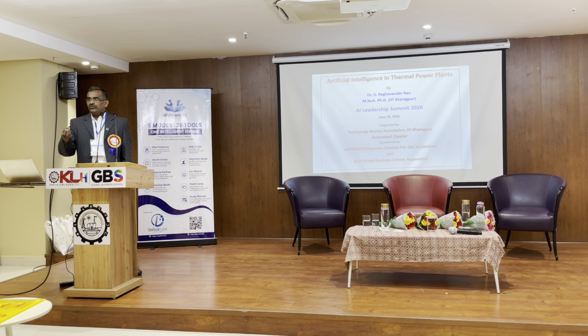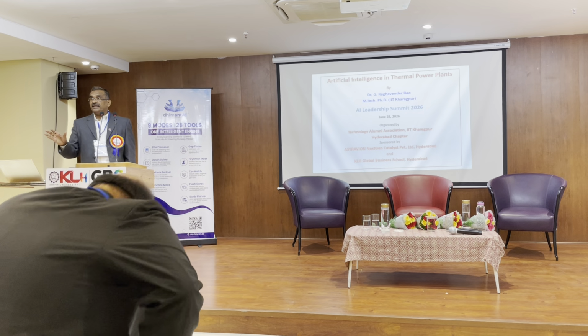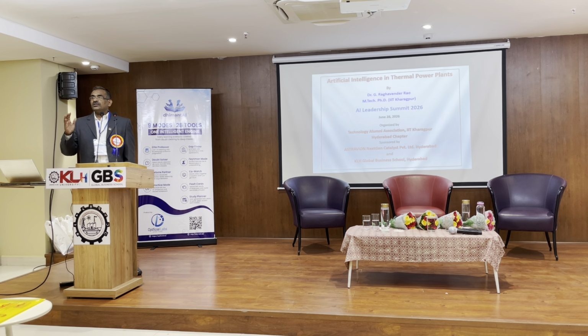If you want to vaporize water, it requires latent heat, which consumes energy. Transferring water to steam below supercritical pressure involves two phases, steam and liquid. But if the pressure is more than 221 bar, water directly converts into steam without requiring latent heat, making the plant very efficient. Higher the pressure and temperature of steam injected into the turbine, higher the efficiency. That's why turbines working with steam above supercritical temperature and pressure are called supercritical thermal power plants.